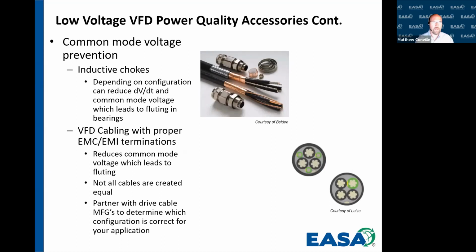Common mode voltage is an issue. Bearing fluting is definitely an issue, and common mode voltages create high frequency voltage in the motor shaft and the frame, so we're going to get fluting potentially as a result of that. You can use inductive chokes. They can also be used to reduce some dV/dt as well as common mode voltage. There are several manufacturers that make those, and they have different configurations. One of the easiest ones is actually VFD cable with proper EMC and EMI terminations.